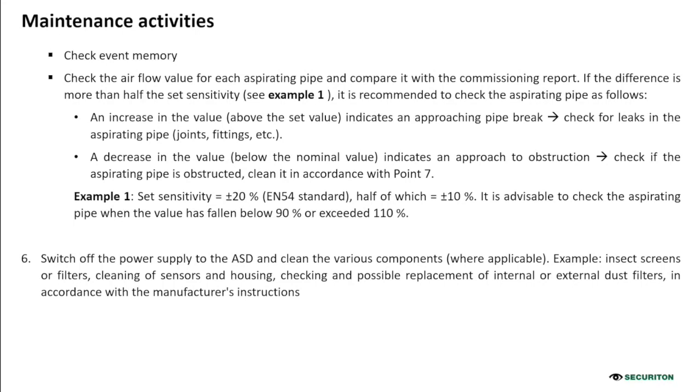Thank you. The second question is, why are ASD systems assimilated to collective smoke detectors with regard to maintenance? Yeah, it's because they generate a zone alarm. So each detector within the ASD system is assimilated to a conventional or a collective line. That is the reason.